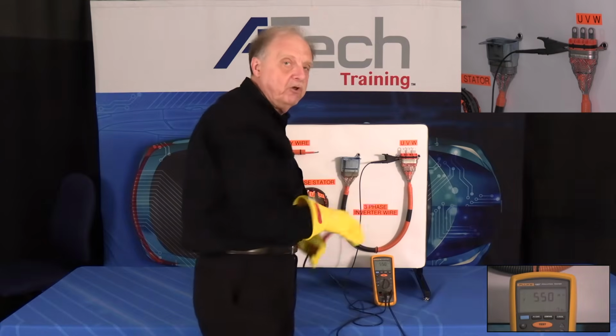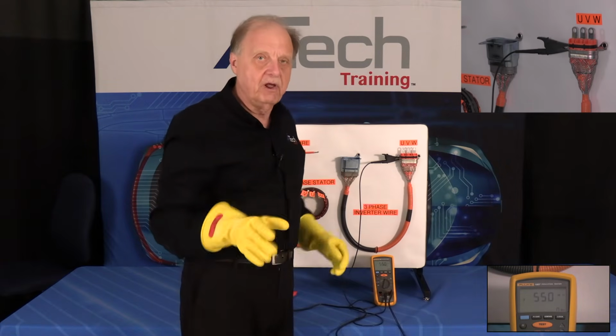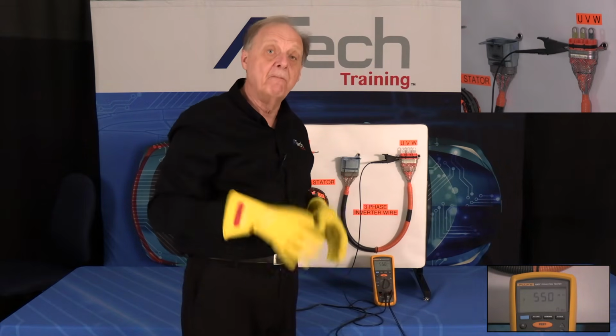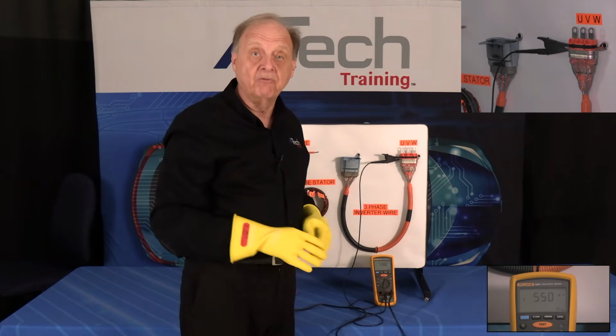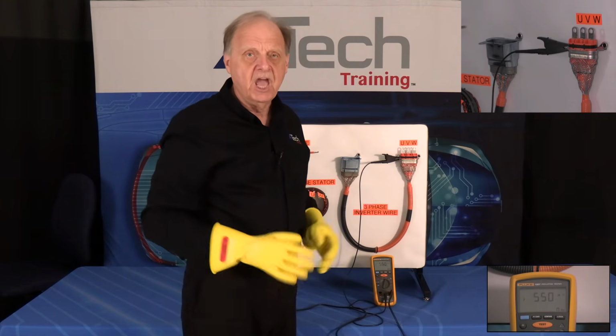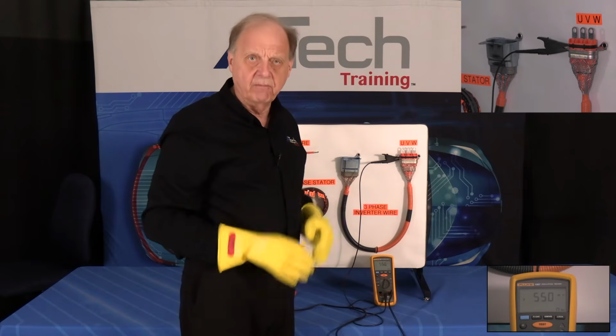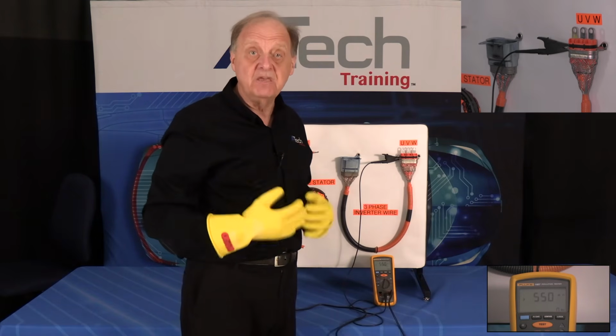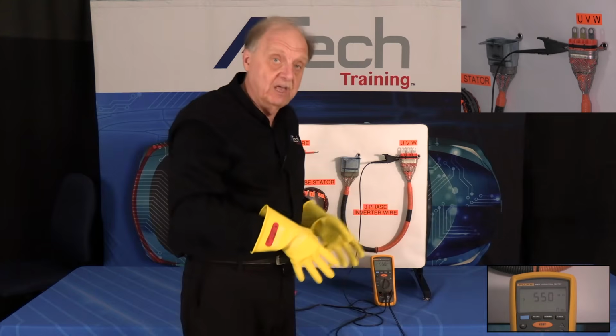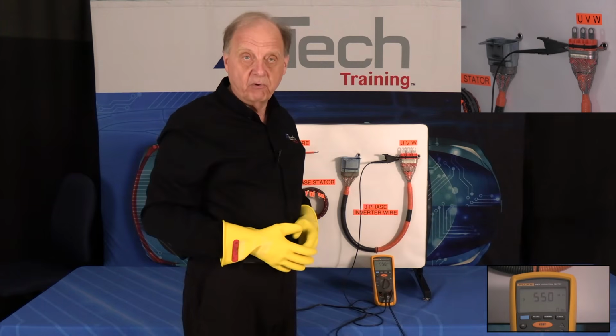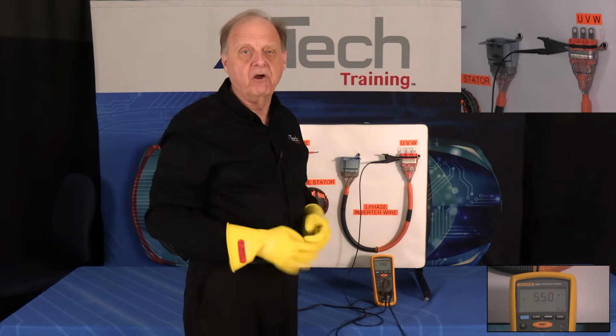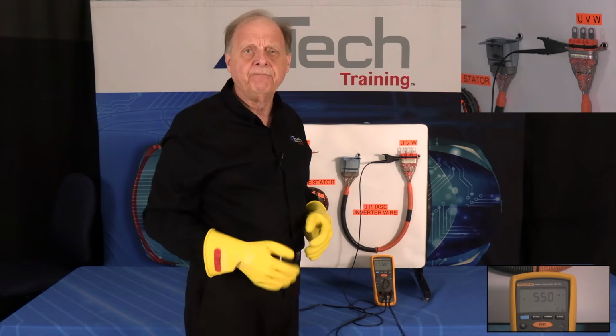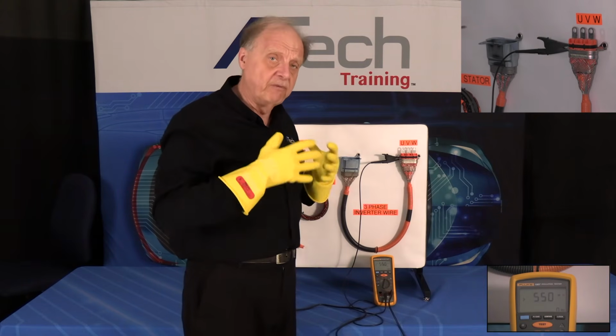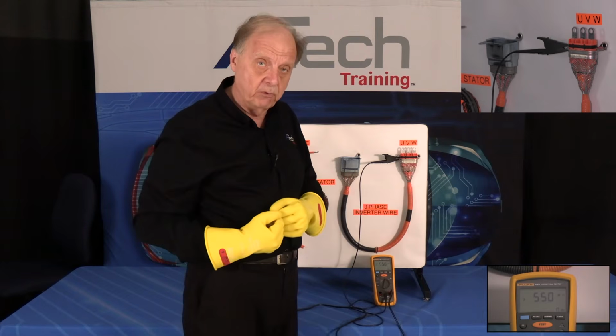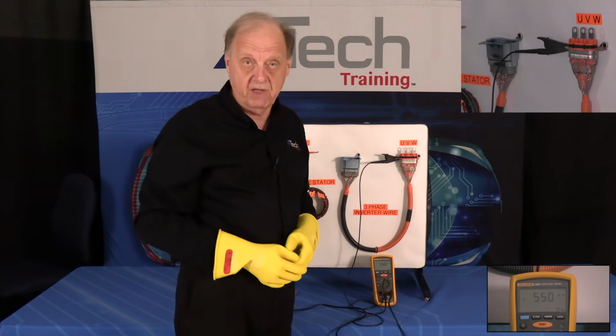Now, before you do this testing, I'll make sure I remind you of this, the system must be shut down. It must have no voltage up there. Anytime you do an ohms testing on the system, the voltage should not be there. You're going to put voltage in it to test it. There should be no voltage there. So make sure that the system is shut down. Some guys call it a live dead test, where they check the voltage and they make sure they check the voltage afterwards to make sure the system is powered down.